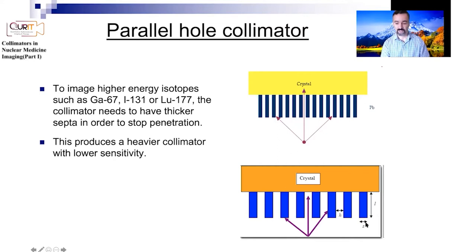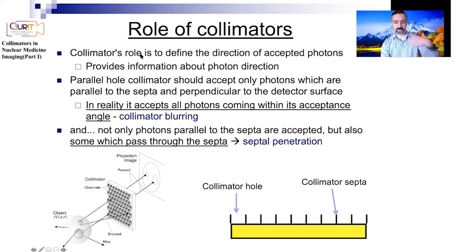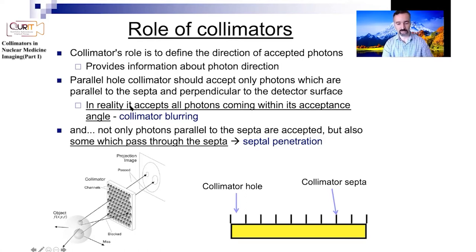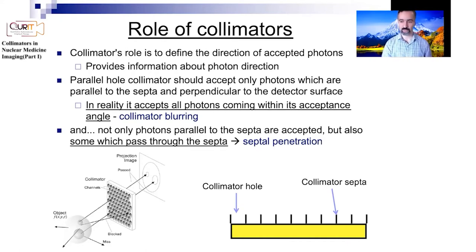For higher energy isotopes like lutetium-177, which is very popular for theranostic applications, you need collimators with thicker septa. The septa thickness s must be larger, which impacts sensitivity, but you have to make the septa thicker otherwise you'll have too much septal penetration. The collimator's role is to define the direction of accepted photons, allowing those perpendicular to the detector surface, though a narrow acceptance angle results in collimator blurring.